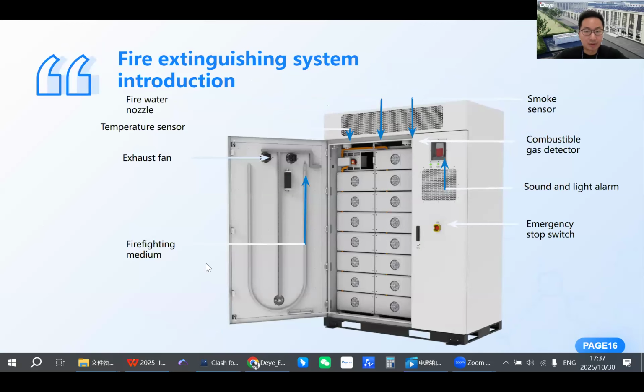And now we come to the actual hardware we put into our system for firefighting and suppression. I will elaborate a little bit here. On top, there is a temperature, combustible air, and smoke detector. These are the exhaust, and that is the air inlet. When combustible air is detected inside the battery cabinet, say carbon monoxide, hydrogen, that kind of thing, usually released when your cells are experiencing thermal runaway, the inlet will pop open and the exhaust port will pop open. They are controlled by an electromagnet. And the exhaust fan will pull the combustible air out of your battery cabinet to prevent an explosion inside. That is an aerosol dispenser.